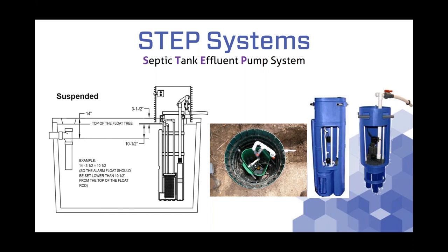The one we're talking about today has a turbine pump — high pressure, low volume systems that work very well for STEP collection systems. Everything is contained inside the vault: the pump, the float switches, and a float tree. A very important feature is that we're flowing the effluent up into the top middle section of the vault, and it'll flow through septic tank filters with 1/16-inch filter screens. These filter any large particles remaining in the septic tank effluent — anything above 1/16 of an inch is filtered out so it doesn't get into the distribution system or the advanced treatment system.